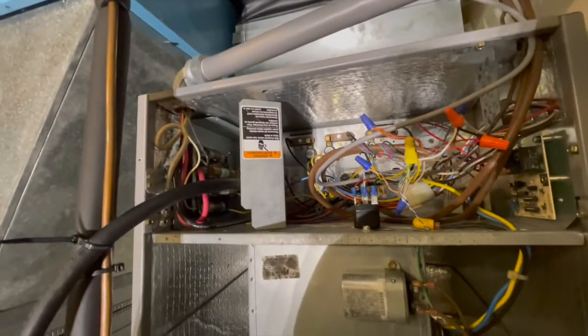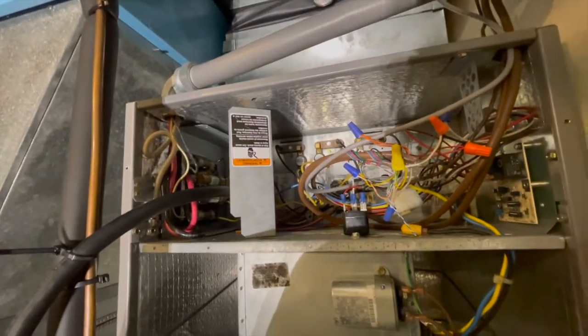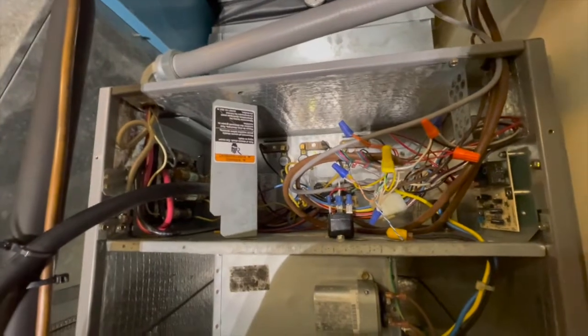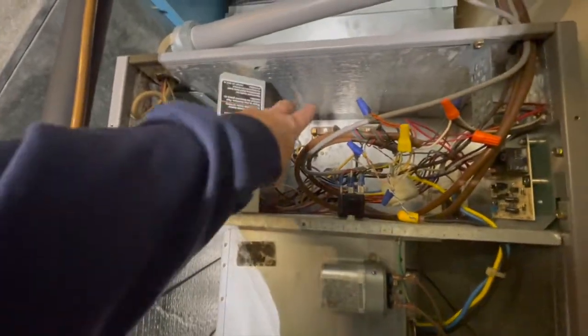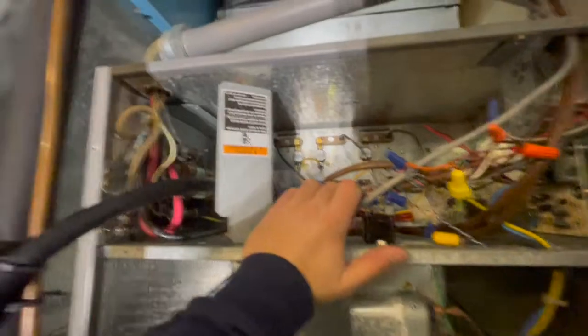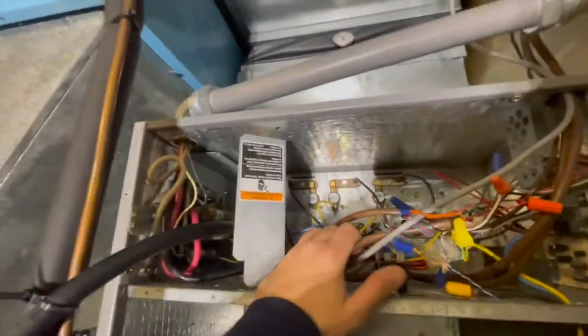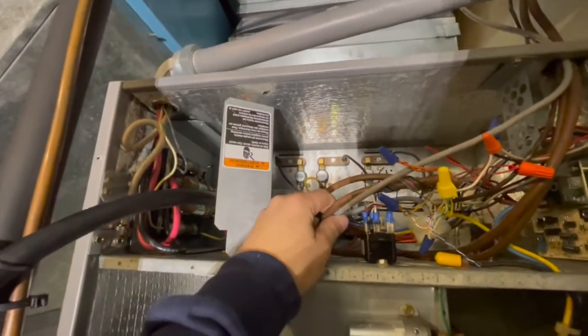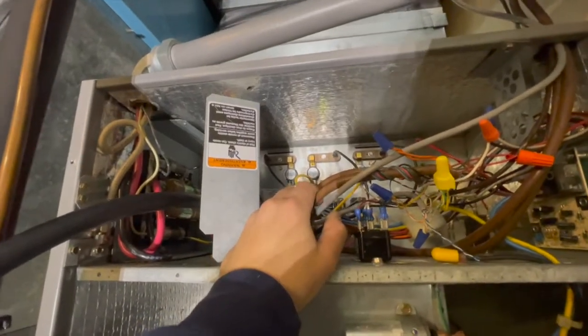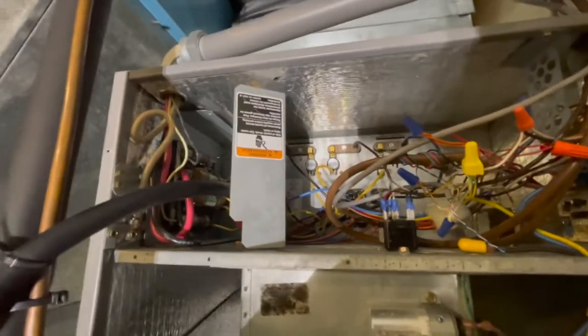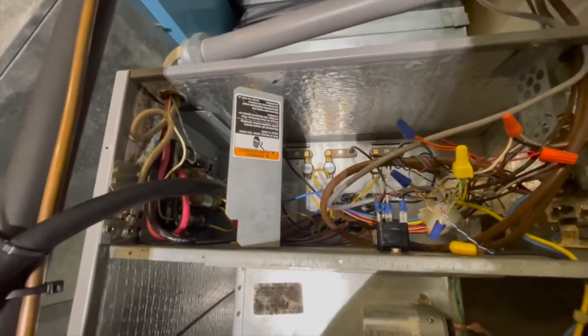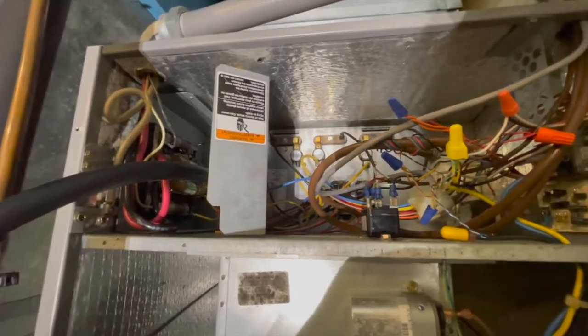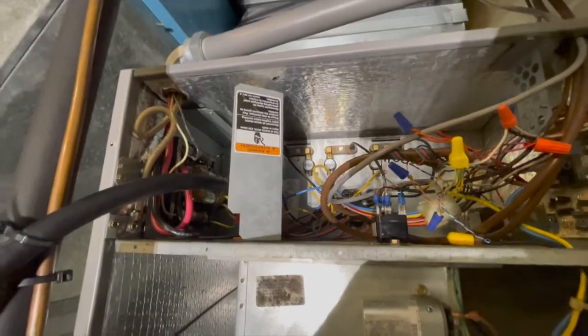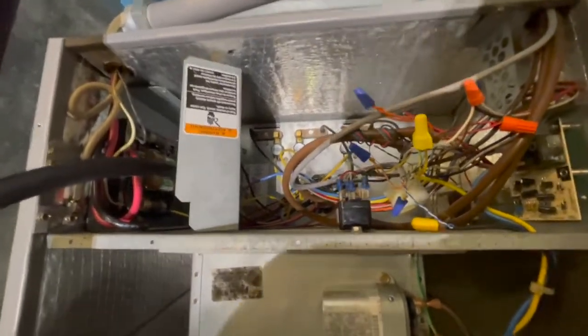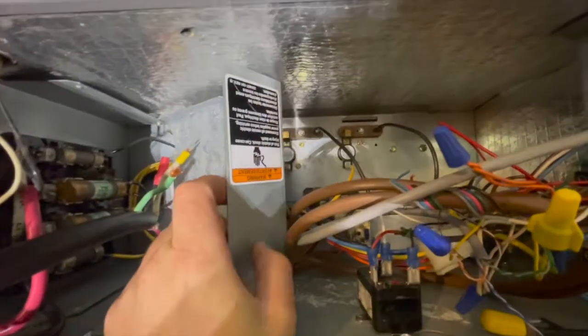So the reason I'm running this today is that I was looking into my heating elements for my house, because my house has electric heat and not natural gas. And I realized that only 2 of the 3 heating elements are being used. Reason being is that the wire going into this unit is underrated, so it's only a 6-gauge wire, can handle maximum 60 amps. And each heating element would be pulling about 22 amps, so you'd be overloading it by 6, 7 or 8 amps if you had all 3 of them. So I guess the previous owner or company only hooked up 2 of them, so that left 1 heating element not being used.